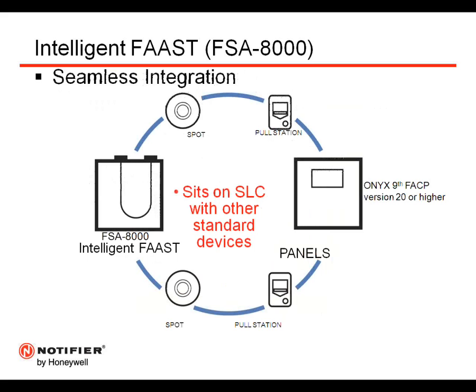It's going to provide seamless integration, and this slide that I'm happy enough to get from System Sensor truly brings it home. If we look at this slide, we just see that the FSA 8000, the Intelligent FAAST units, just sits directly on the SLC loop with our standard spot detection, pull stations, and modules, and all the rest of the addressable devices that sit on the SLC loop.